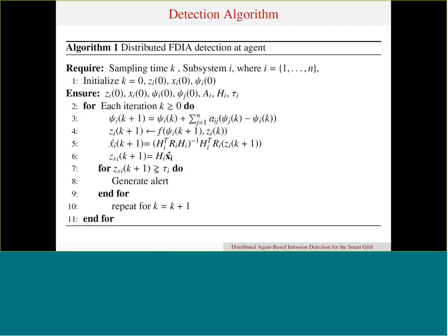After they've run consensus, based on the data they get from their neighbors, they will run another state estimate, and then they will double check if this state estimate lies within the allowable operation range of their system. If agents do this at every iteration, when they converge, they will all know if any new command is going to put the power grid in an insecure state, and they'll all know if there's been any tampering with the measurements at any of the subsystems they've created. Because, as we mentioned earlier, agents partition the power grid into logical partitions. So that's basically the algorithm that each agent would run.